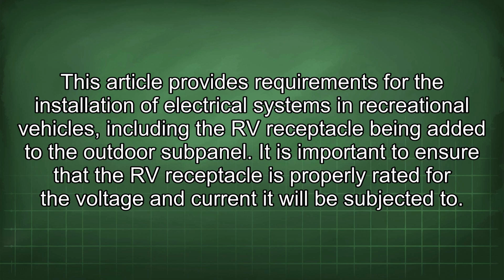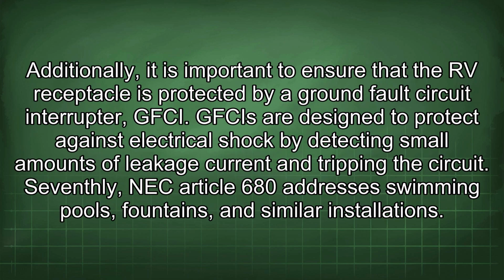the outdoor subpanel. It is important to ensure that the RV receptacle is properly rated for the voltage and current it will be subjected to. Additionally, it is important to ensure that the RV receptacle is protected by a ground fault circuit interrupter, GFCI. GFCIs are designed to protect against electrical shock by detecting small amounts of leakage current and tripping the circuit.